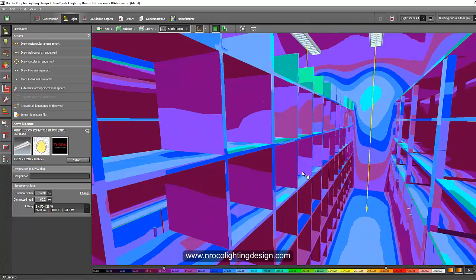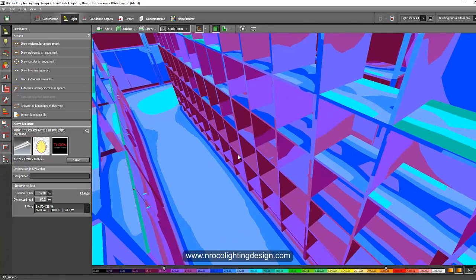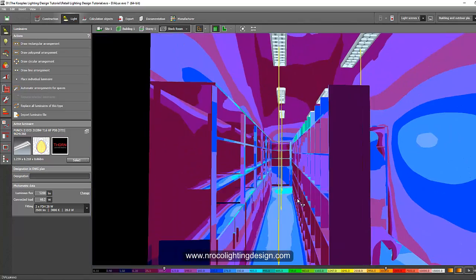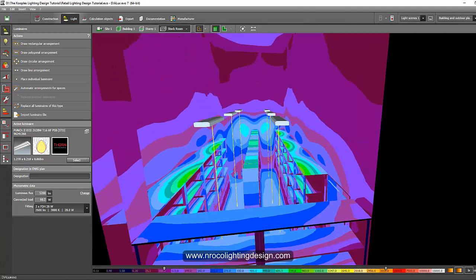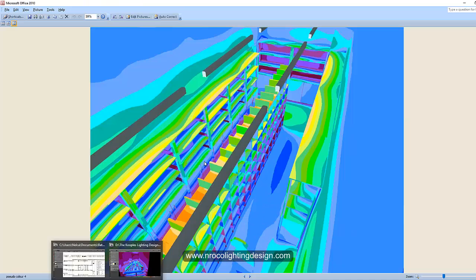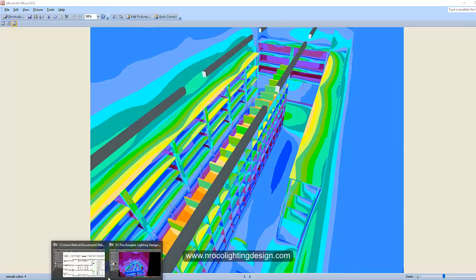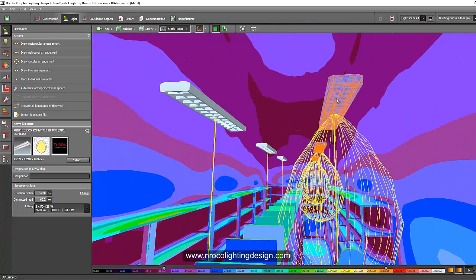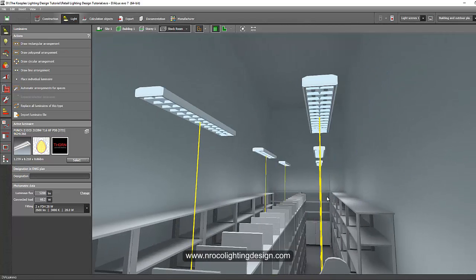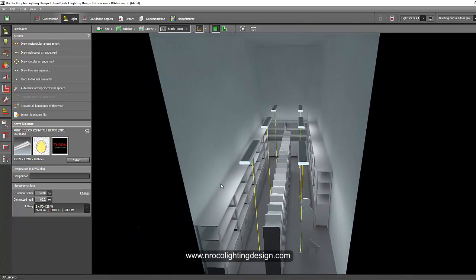The stockroom shows 300 lux on the floor, 600 to 300 lux on the shelvings, but this area is only 100 lux — that's showing purple in false color. We're trying to achieve 500 lux at the bottom but it's not quite there. This is fine compared to the first version which was really bright. The luminaire selected is a 2x28W louver fitting — fluorescent, not LED. Let's continue editing the aiming on the other file.